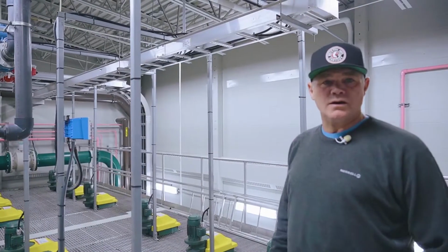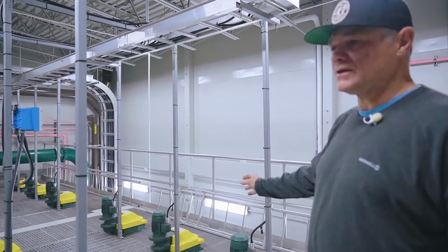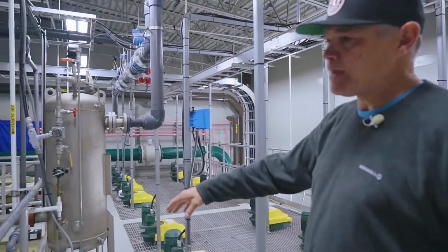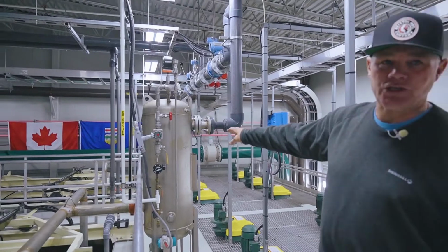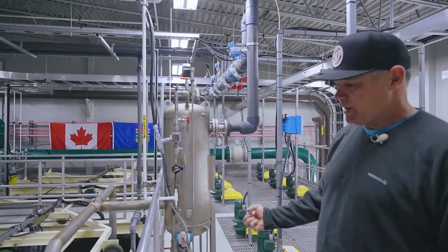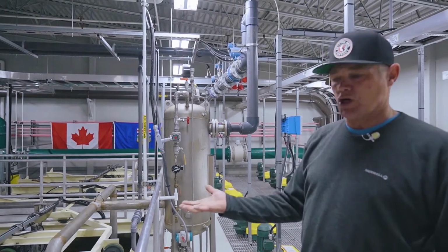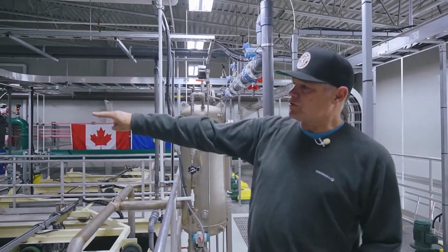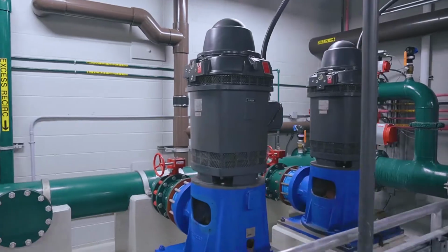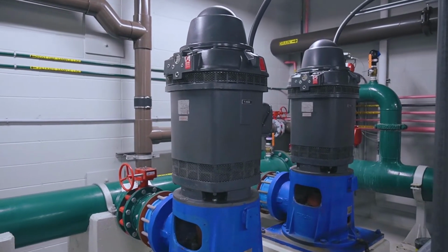So after the water goes through the primary and secondary flock tanks, it goes into the dissolved air flotation tank. This is a saturation tank, and it mixes water and air together and makes a micro bubble. And it keeps all of the dirt and solids on top of the DAF. The 2 pumps over here, the saturation recycle pumps, keep the water coming into the saturation tank.